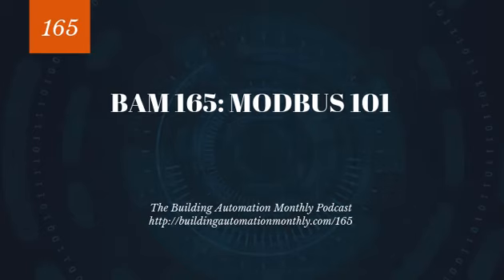Now, normally I'm not someone who sits here and recites terms. I don't sit and spend entire episodes going through terminology, but with Modbus, it's important that we understand these 3 terms. First of which is called the ADU. Now, the ADU is the Application Data Unit. And for Modbus, the ADU is going to encompass the PDU, which is the Protocol Data Unit. So the ADU is going to be handling things like error checking. It's going to be conveying maybe additional addresses if you're sending bulk messages, which most of you are not. Most of you are going to be doing single messages. You're not going to be doing bulk messages.